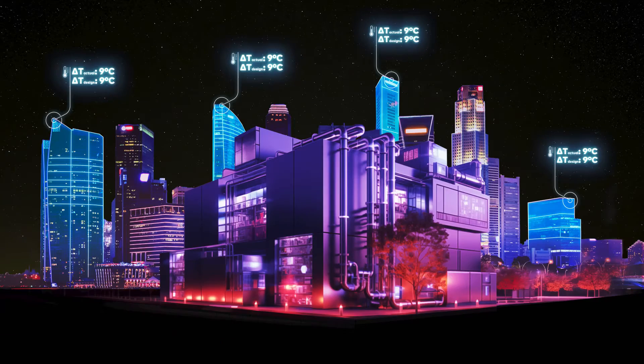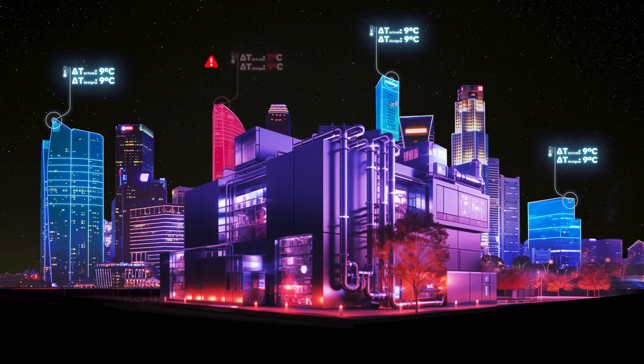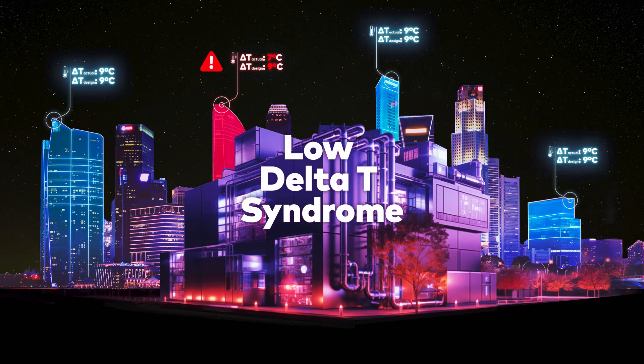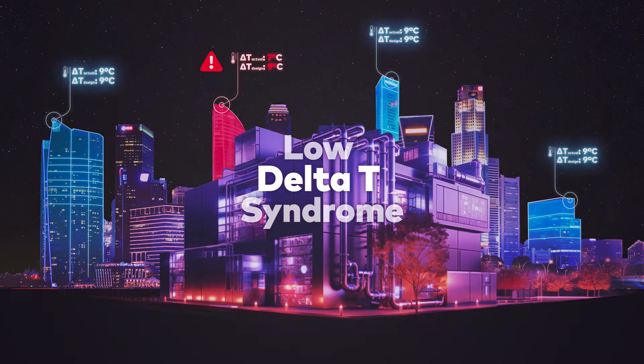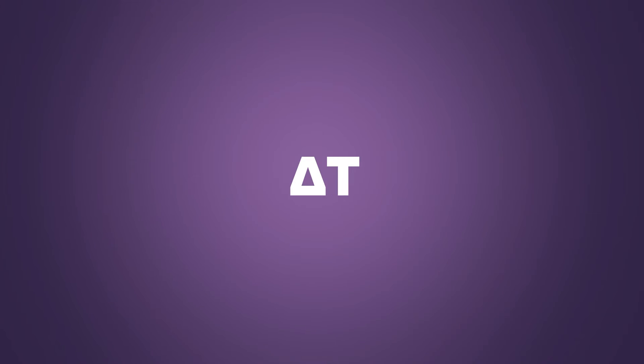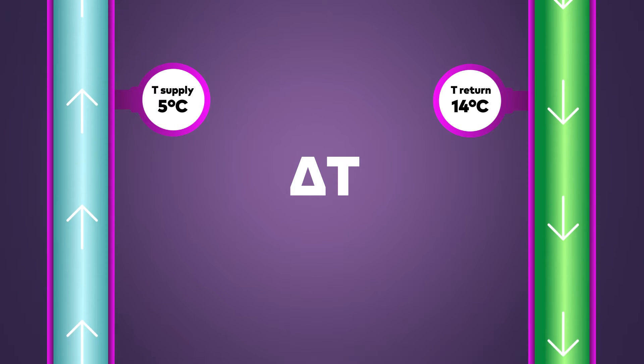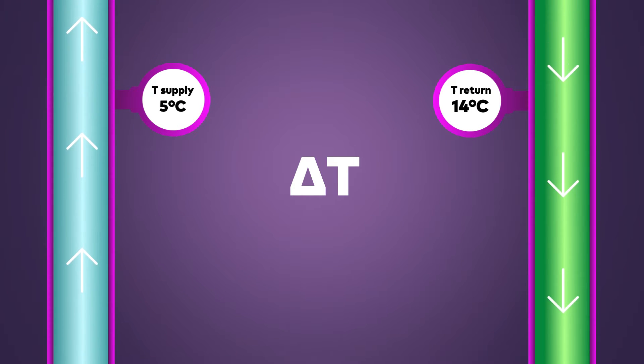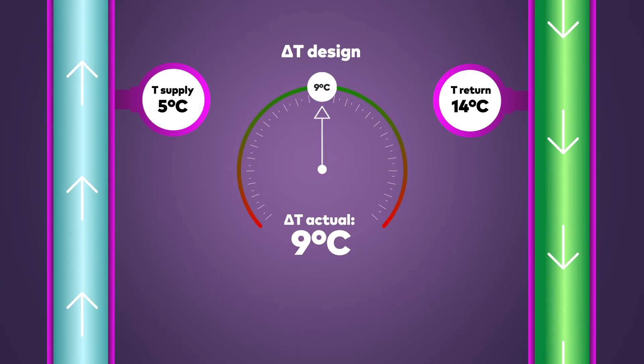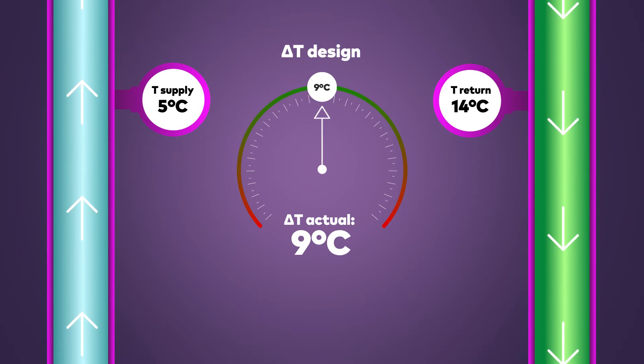Today we're exploring a specific HVAC challenge in buildings known as Low-Delta-T Syndrome. But before we dive into this, let's first understand what Delta-T means. Delta-T is the temperature difference between the supply and return water in an HVAC system. This fundamental concept can tell us a lot about how efficiently your HVAC system operates.